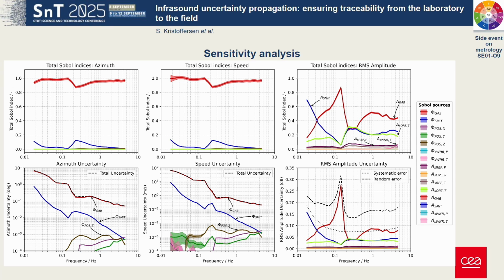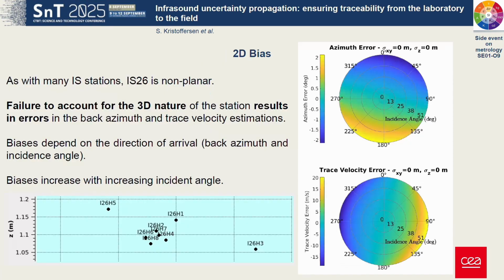And I'll just note too that, because it may be hard to see some of the numbers, but these uncertainties aren't huge, so don't look at it and go, okay, the Gabrielson calibration is almost 1 in the Sobol index. It's a huge value, but then when you look at the actual contributions, so for example at 1 hertz, we're looking at about 1/10 of a degree in uncertainty. So these aren't huge contributions, but when we're only taking into account these calibration uncertainties, those are the most important ones. So now we'll just quickly talk about some of the effects of 2D bias.